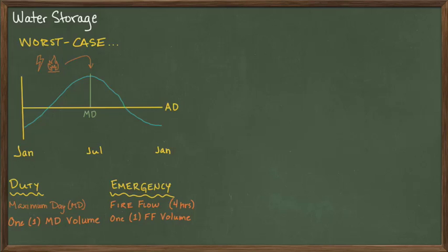Once you have these two values, then the storage requirement is the volume of one max day plus the volume of required emergency flow or fire protection. Let me pause for a moment just to say that each water agency has slightly different words for these values and may also have slightly different ways of computing these volumes. In the absence of any other guidelines, these are sufficient to get a conservative estimate for the water storage required.